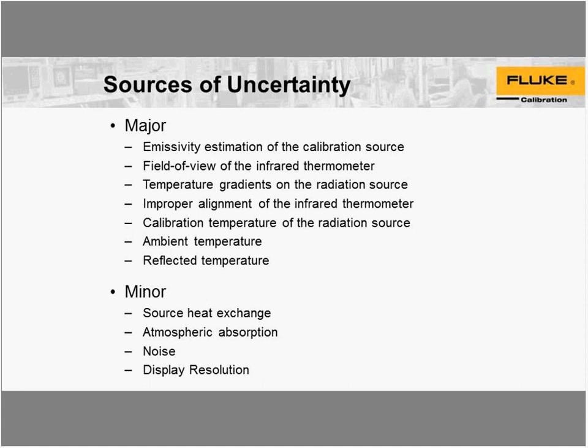Sources of uncertainty you need to consider — I've classified these as major and minor. The major ones are especially important when setting up your laboratory and doing calibrations. Number one is emissivity of the calibration source, then field of view of the infrared thermometer, target size relative to the IR thermometer, temperature gradients of the radiation source, alignment of the infrared thermometer, calibration of the radiation source itself, ambient temperature, and reflected temperature. Minor sources that still need consideration include source heat exchange, atmosphere absorption, and display resolution.